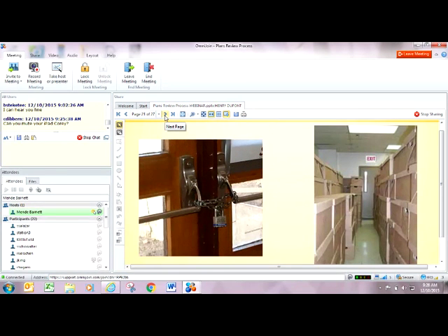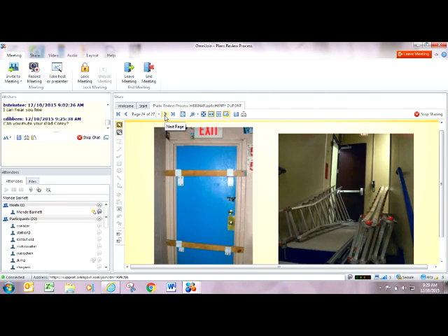On the right, we see a problem that's quite frequently found where supplies for the new construction, whether it's construction materials or furniture, that sort of thing, are stacked and stored in the corridors. In this case, it definitely narrows the corridor to the point that we would have a serious issue with that. Same on both of those. These are problems that we're going to see.